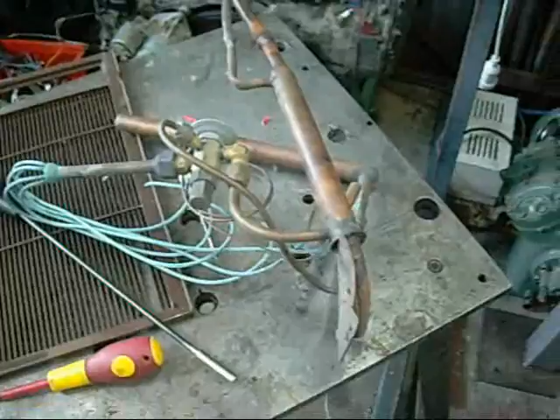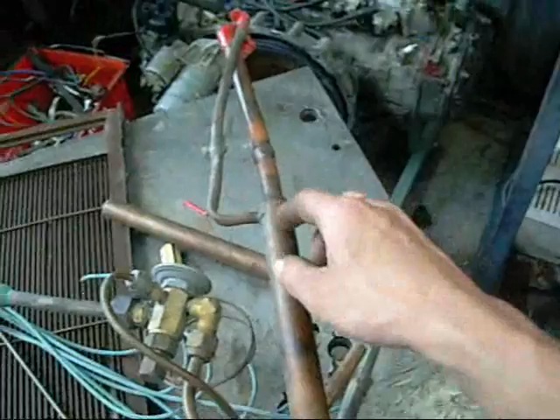Just looking at this assembly here, I noticed it's got a little heat exchanger where you've got liquid into the outside of this manifold and then to the TX valve, and it does two things. It will help evaporate any liquid coming back down here, because the liquid coming in will be warm, presumably. A lot of air conditioners you'll find the capillary tube or the liquid line runs warm. So it'll help remove or evaporate any returning liquid that might get back to the compressor, and likewise the low temperature of the suction line gases will also help remove any excess heat from the liquid.